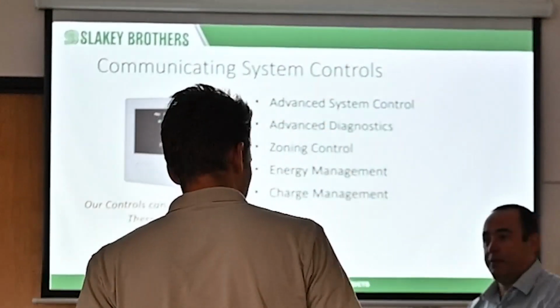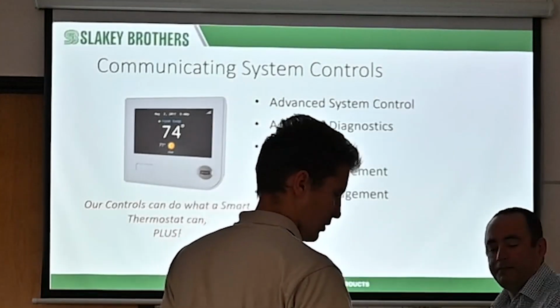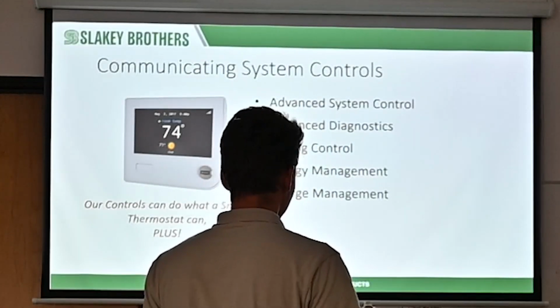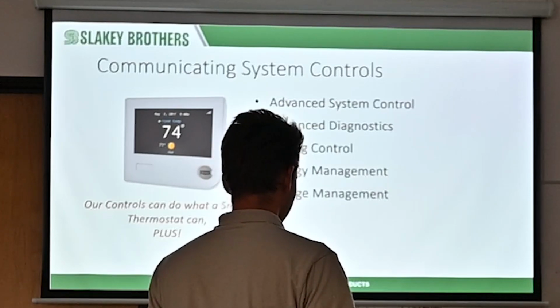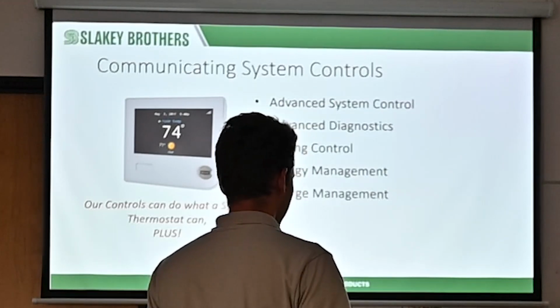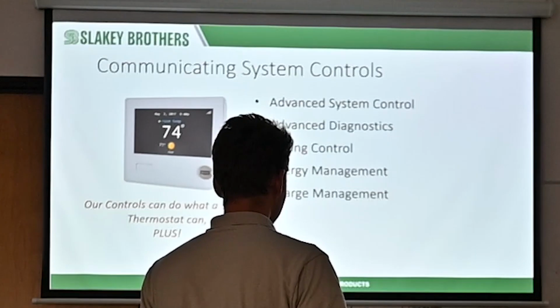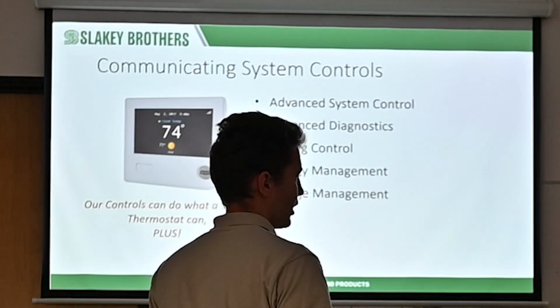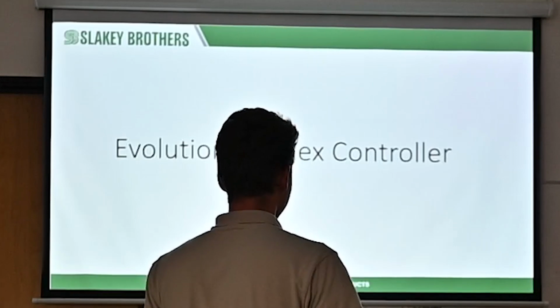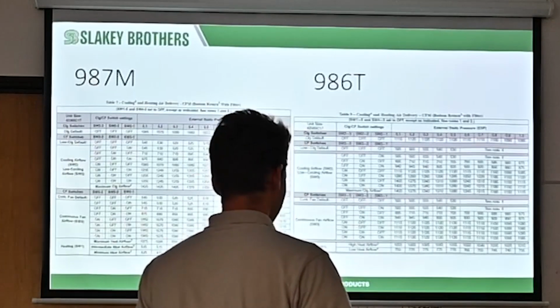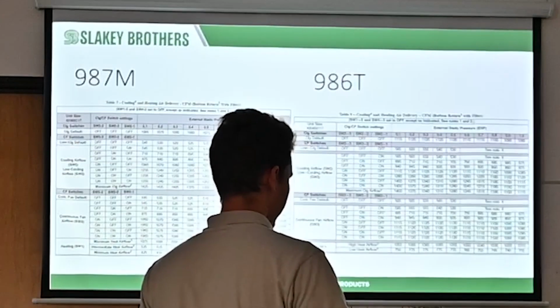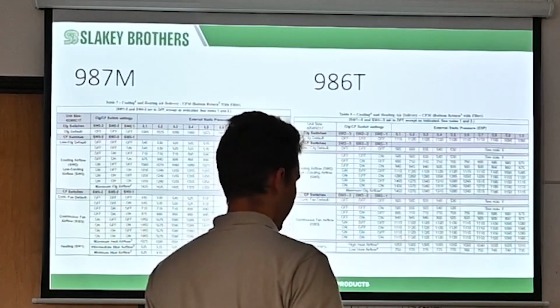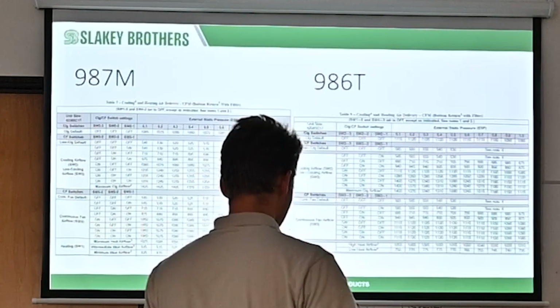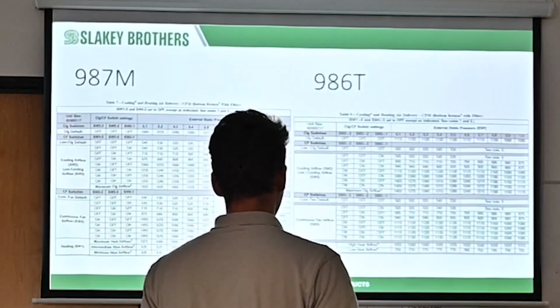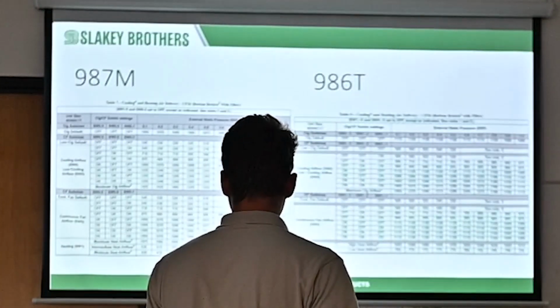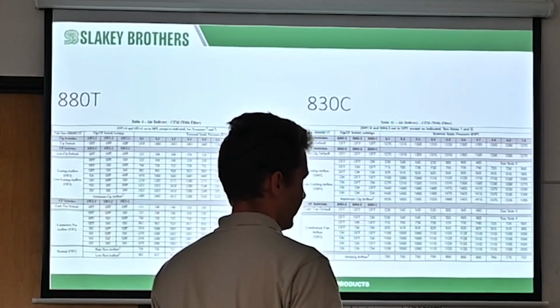Excuse me. Yes. I have two cases which I want to ask you about. I don't know, maybe when it's better to ask. The first case is about a communication problem, and the second one is about the dip switch airflow adjustment. I have a system with an air handler, and it adjusts itself to about 2000 CFM, and it's turning off by the pressure. Static pressure? Yeah, static pressure. Excessive static pressure.